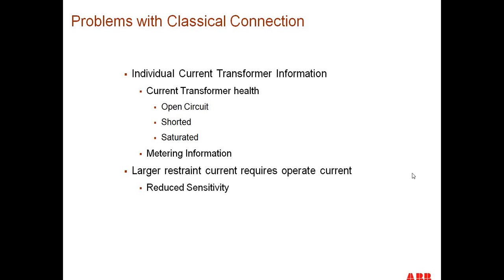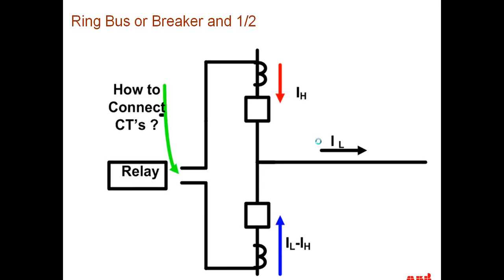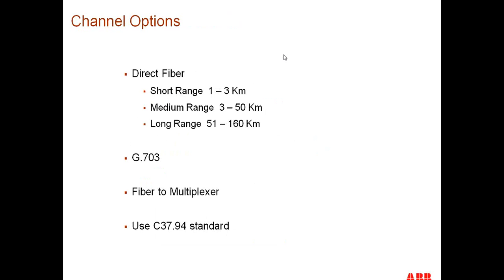Another question came in: the C37.94 standard permits greater than 160 kilometers length fiber. Actually, the C37.94 doesn't really say anything about line lengths at all. The limitation on the length of line that you can have with a fiber is dependent upon the losses on the fiber and the amount of the receiver sensitivity and transmitter capability of the current differential relay scheme itself. They don't really deal at all with C37.94. What I gave as an example previously was just talking about the limitations that we normally define for different lengths of line, not what C37.94 defines these lengths of line to be.